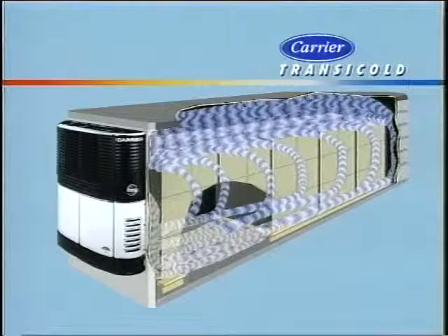Just a word of caution. Anytime the start-stop light is on, the unit is programmed to start automatically without any help from you. Our unit is now running the auto start-stop mode. This means that the unit will run until box temperature is the same as the set point. Once box temperature and set point are the same, the unit will cycle off and remain off until it is needed once again to bring box temperature back to set point.